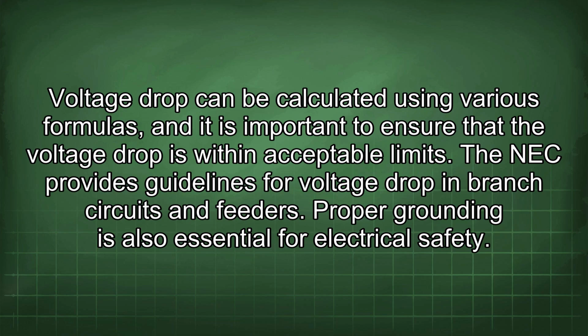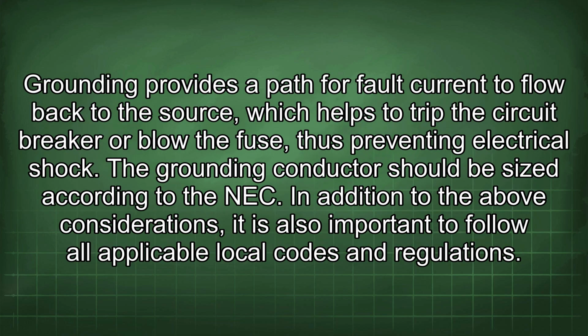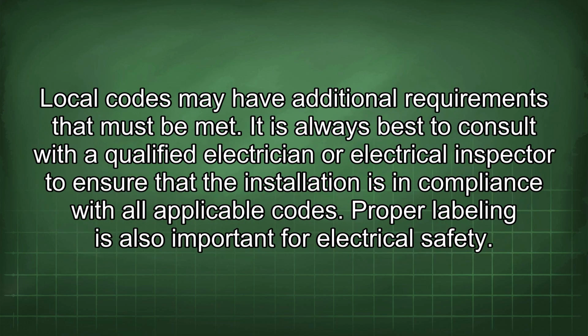Proper grounding is also essential for electrical safety. Grounding provides a path for fault current to flow back to the source, which helps to trip the circuit breaker or blow the fuse, thus preventing electrical shock. The grounding conductor should be sized according to the NEC. In addition to the above considerations, it is also important to follow all applicable local codes and regulations. Local codes may have additional requirements that must be met. It is always best to consult with a qualified electrician or electrical inspector to ensure that the installation is in compliance with all applicable codes.